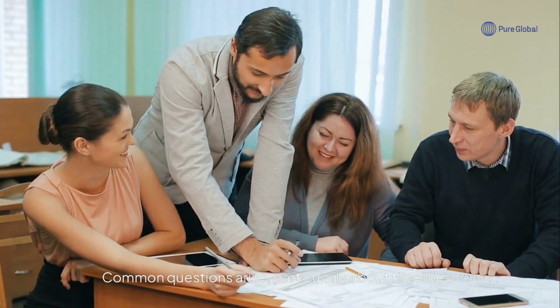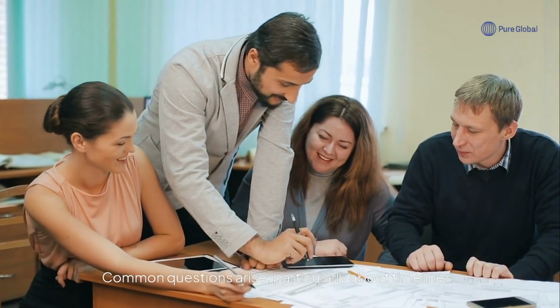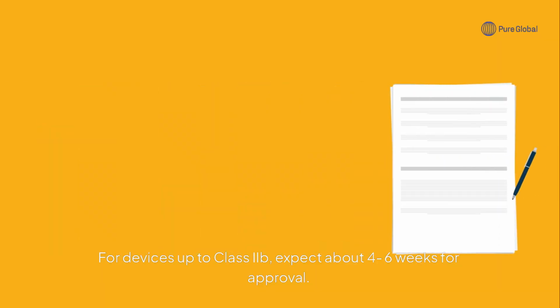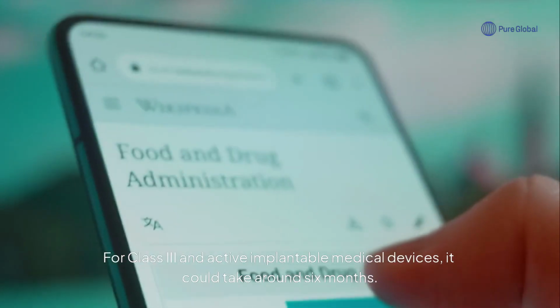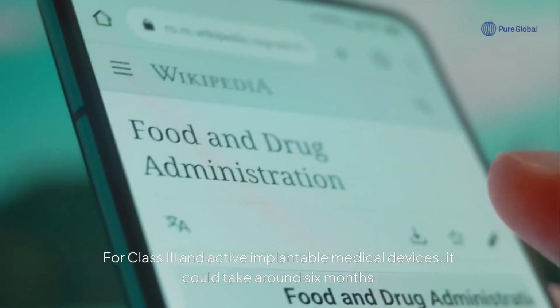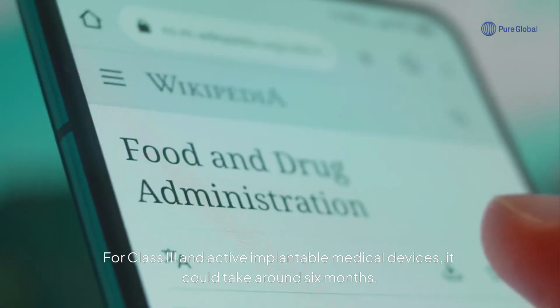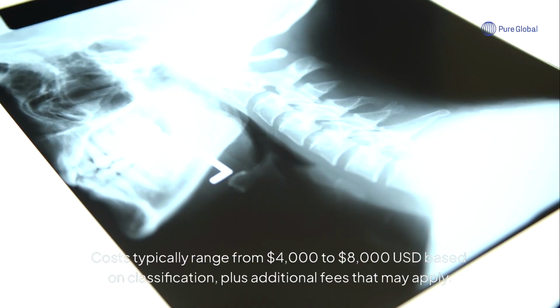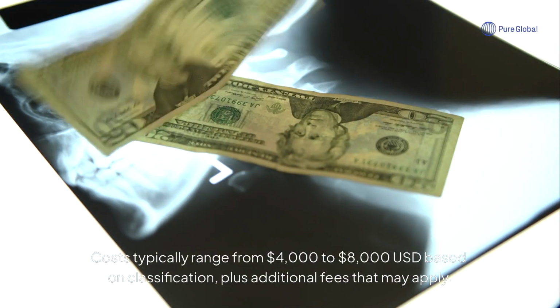Common questions arise, particularly about timelines. For devices up to Class 2B, expect about 4-6 weeks for approval. For Class 3 and active implantable medical devices, it could take around 6 months. Costs typically range from $4,000 to $8,000 USD based on classification, plus additional fees that may apply.